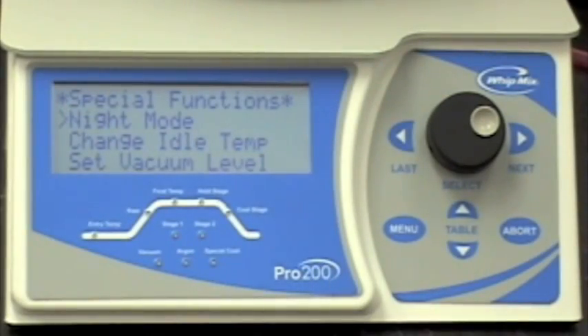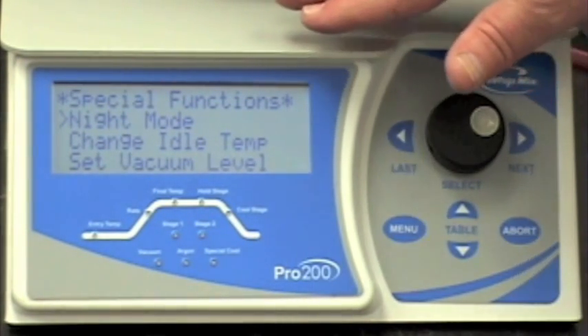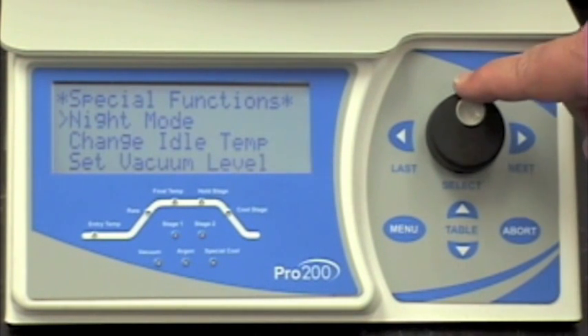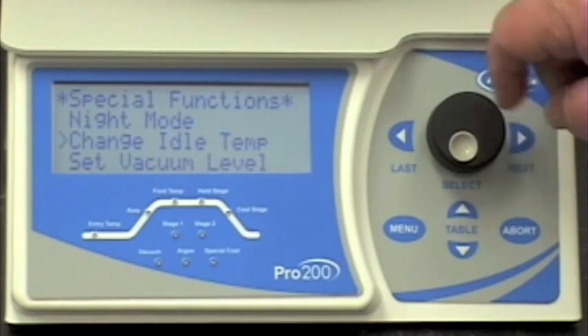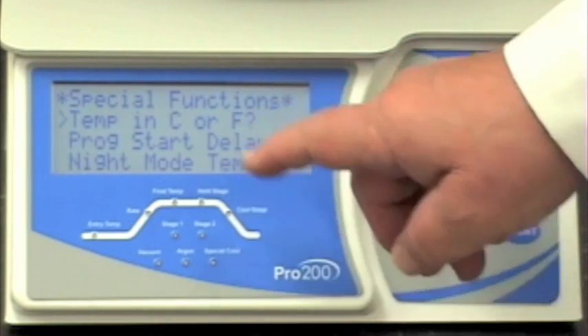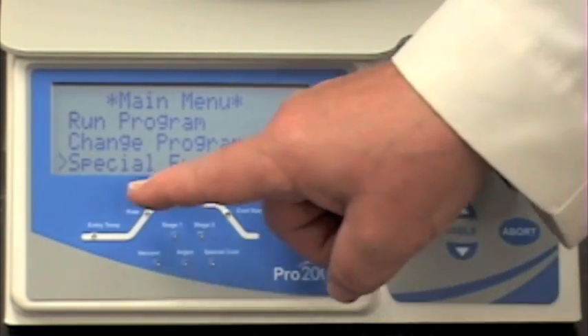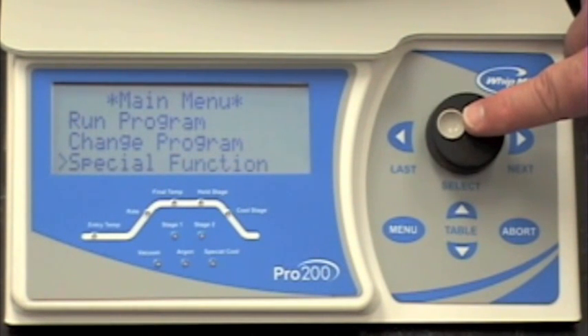Now that you've arrived at the special functions menu, the first thing you're going to want to do is determine whether your machine will operate in units of Celsius or Fahrenheit. To get to the special functions menu, rotate the selector knob until the cursor arrives at the special functions menu, then press the selector knob to enter.